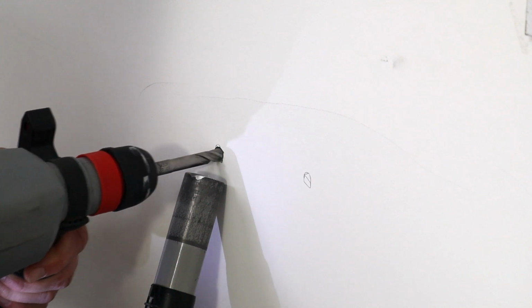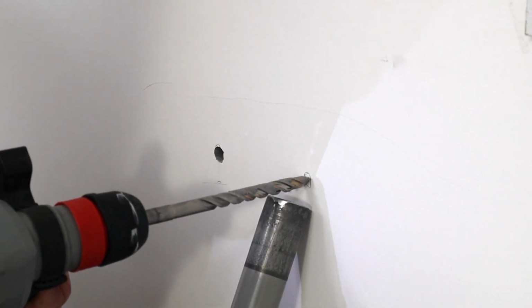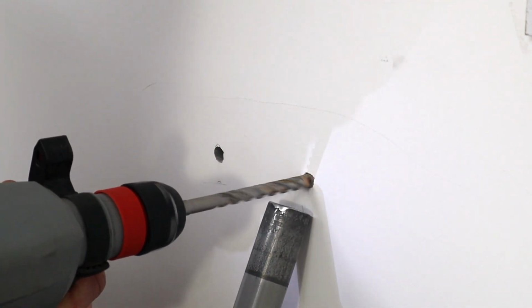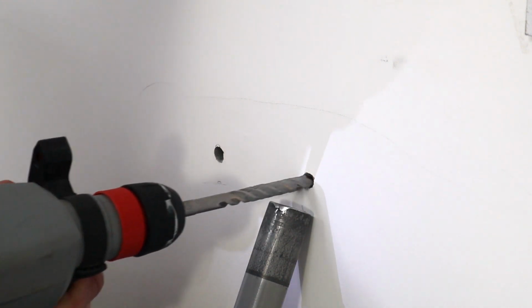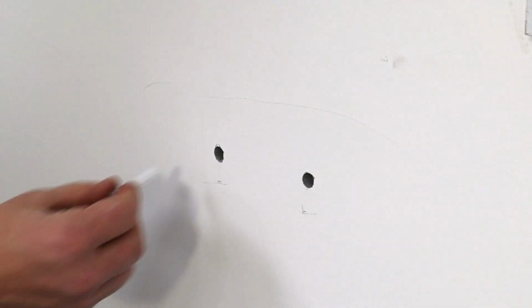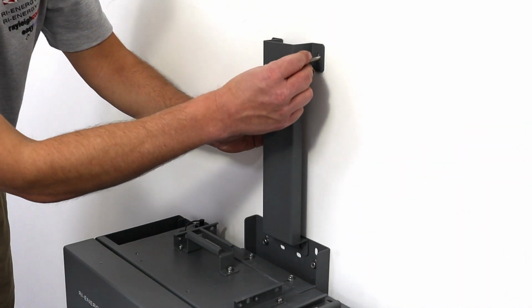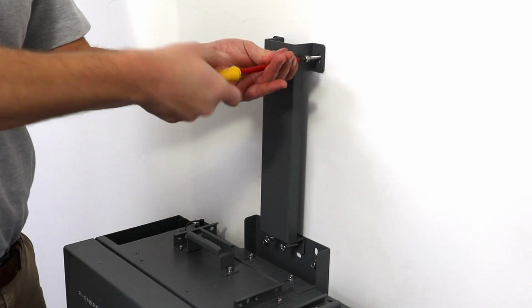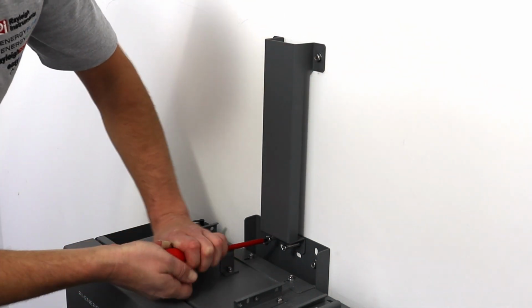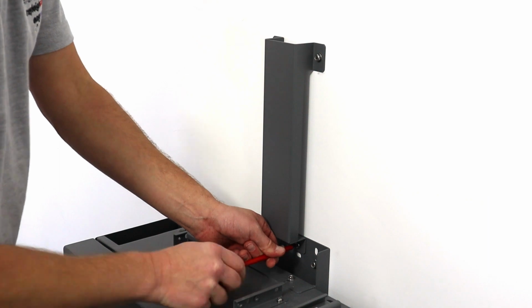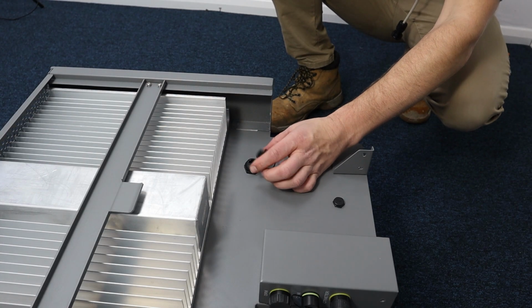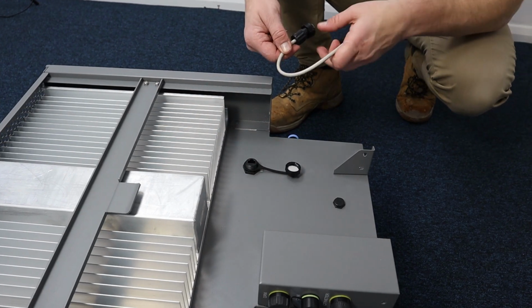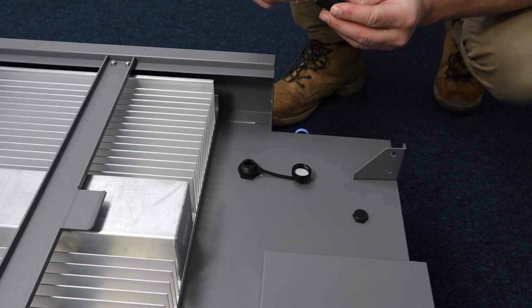Drill the holes with an 8mm drill bit to a depth of 70mm as before. We recommend you use a vacuum cleaner or some other dust collection method so that the dust does not collect on the batteries that you have installed. Place the roll plugs and fix the bracket firmly into position using the 4 fixing positions. Connect the supplied inverter battery communication lead to the plug located on the back of the inverter.